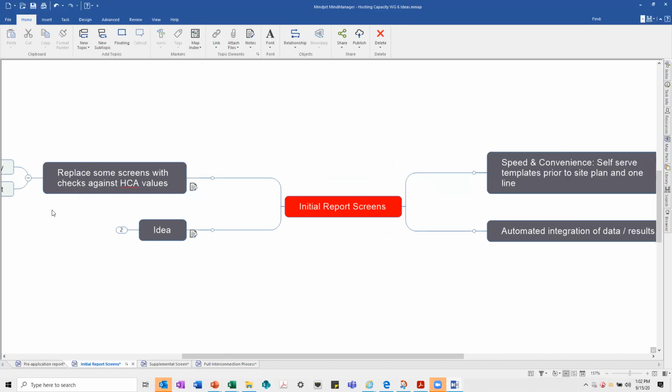I would also just add that the whole reason why the construct of hosting capacity analysis was created in the first place, as I understand it, was to serve as a replacement for the penetration screen that Brian mentioned of 15%, and to be able to provide a more detailed look at a location on the feeder that might enable the interconnection of projects where there is greater than 15% penetration based on capacity value, to let some projects move through in a fast track process. And so, considering that was kind of where the genesis of the hosting capacity analysis came from in the first place, it really seems like that's a conversation that we should be prepared to have today.